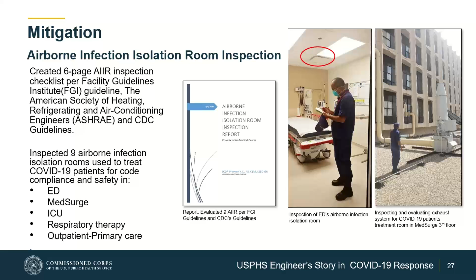Understanding CDC guidelines and life safety code NFPA 101 and healthcare facility code NFPA 99 is very important when inspecting isolation rooms. Knowledge of ASHRAE 170, especially for airborne infection isolation rooms, is a must when evaluating infection isolation rooms. Next slide, please.